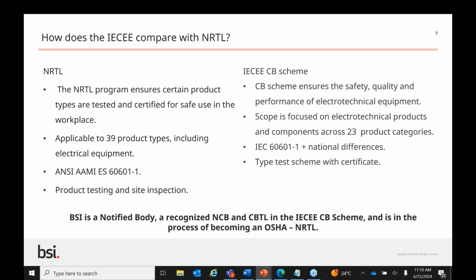So the CB scheme benefits several stakeholders. It can benefit governments as it reduces barriers to trade. It can benefit the industry as it reduces the need for repetitive testing. And ultimately, it benefits the end user or consumer in that a product has been independently tested. Both NRTL and the CB scheme use the 60601 series of standards. So the AAMI published the US amendments of IEC 60601 parts standards in March 2022, and these are now part of the FDA's recognized standards and OSHA's list of test standards. And a similar set of standards was also published by CSA.